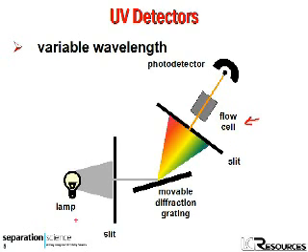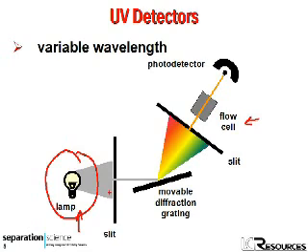Generally speaking, a deuterium lamp is used as the light source, and that generates a broad spectrum of wavelengths — usually in the 200 to 300 nanometer range. Part of this light goes through a slit and is imaged onto a movable diffraction grating, and the resulting spectrum is dispersed and imaged onto an exit slit that allows only a narrow range of wavelengths to pass through the flow cell.